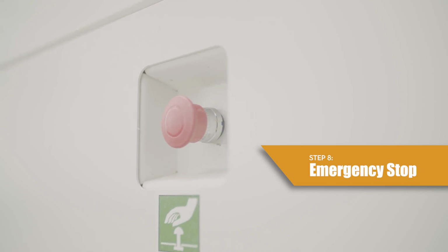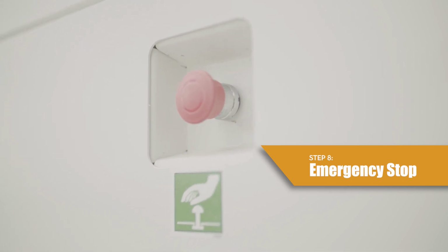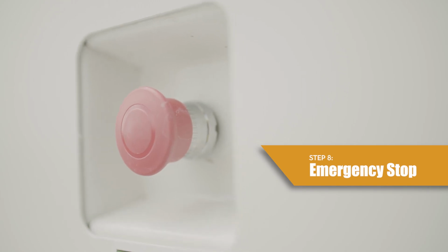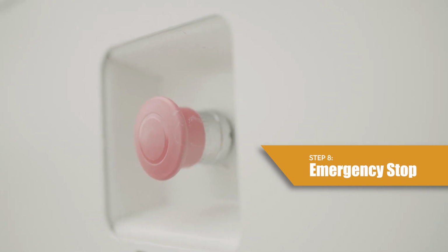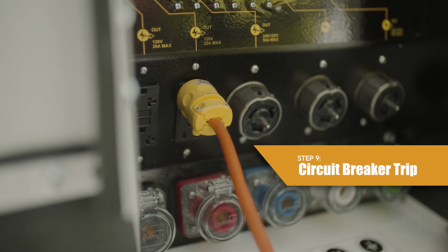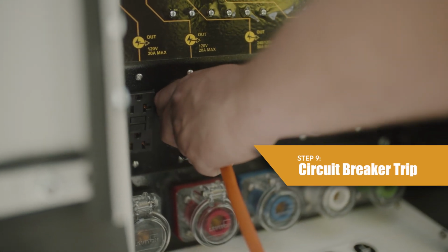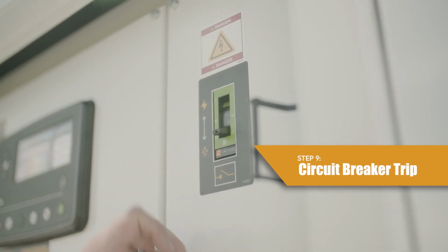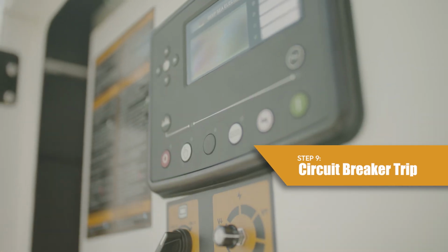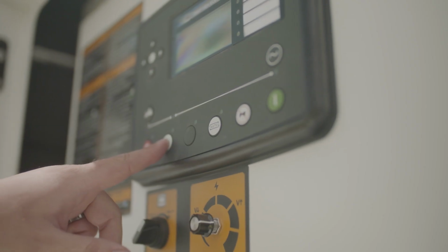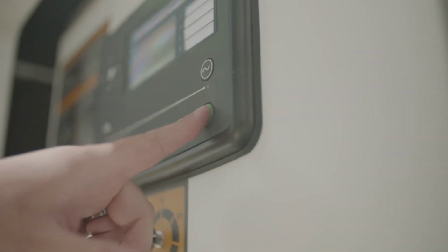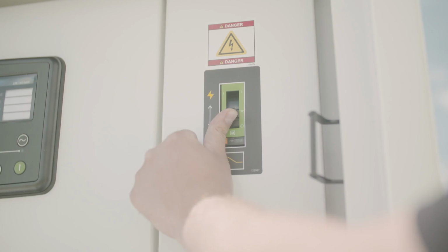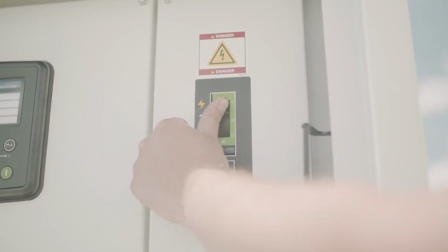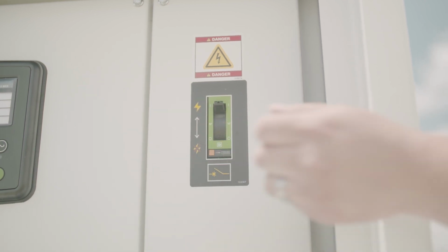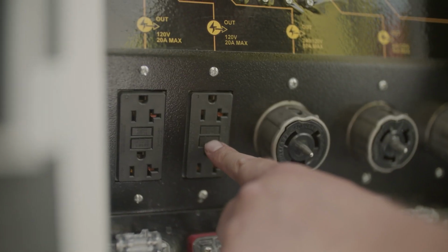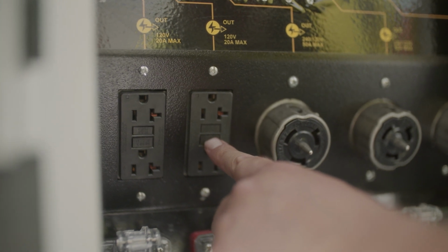Step 8. The unit has an emergency stop button that will immediately shut down the unit in case of emergency. The emergency stop button is located on the rear side of the generator unit. Step 9. If a circuit breaker trips, disconnect the load from the outlet. Switch the main circuit breaker to the off position and shut down the engine. Wait 10 minutes for the generator to cool down. Correct the load problem. Start the engine and switch the main circuit breaker to the on position. Reset the breaker to the on position. Note: also be sure to check the GFCI breaker on the GFCI outlet and reset if necessary.